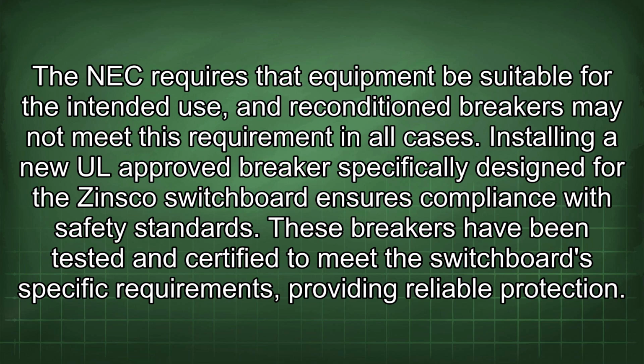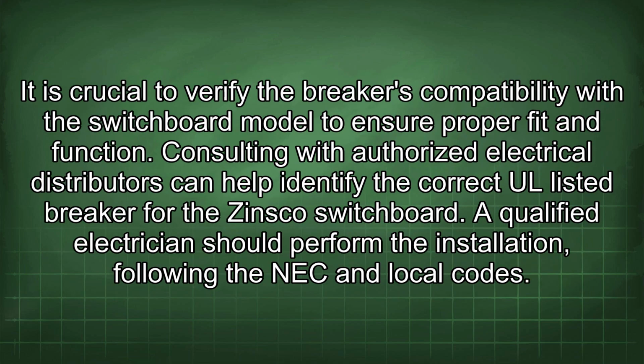Installing a new UL-approved breaker specifically designed for the Zinsco switchboard ensures compliance with safety standards. These breakers have been tested and certified to meet the switchboard's specific requirements, providing reliable protection. It is crucial to verify the breaker's compatibility with the switchboard model to ensure proper fit and function.